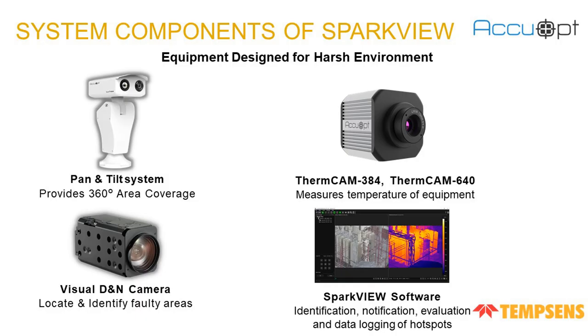These are the system components of our system. Our equipment is designed for harsh environments, and it consists of one pan and tilt system which provides 360-degree area coverage, the thermal camera, which can be ThermCam 384 or ThermCam 640, which can measure the temperature of equipment. It also consists of a visual day and night camera to locate and identify faulty areas, and also our dedicated software, SparkView software, for identification, notification, evaluation, and data logging of hotspots.